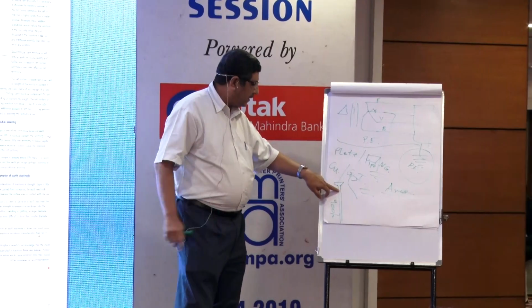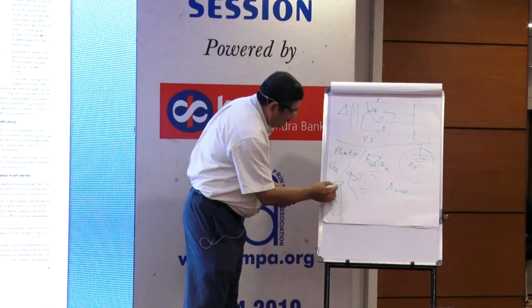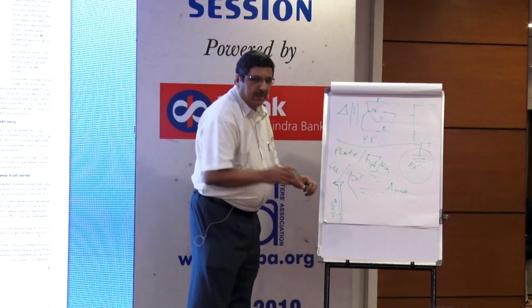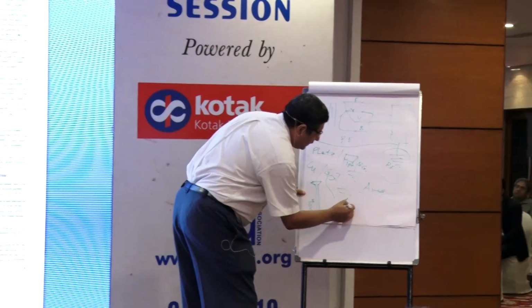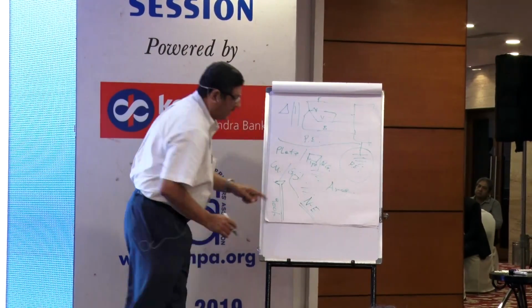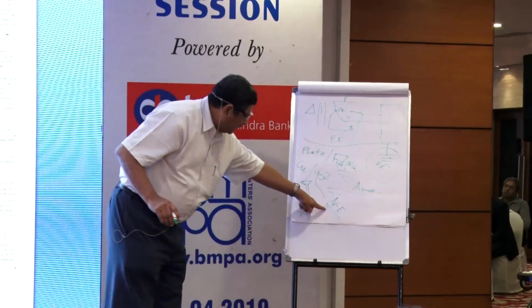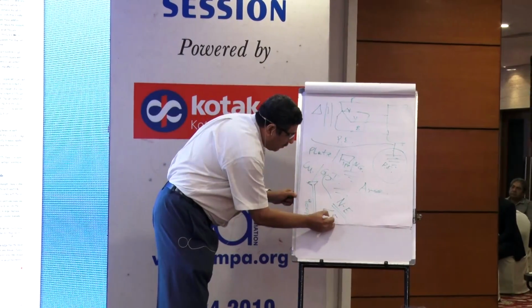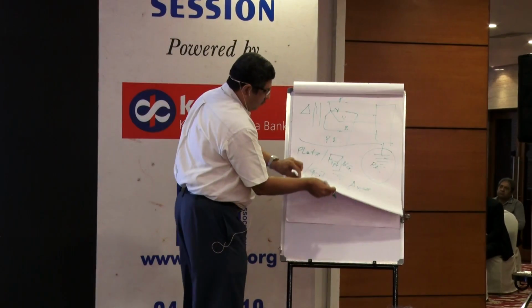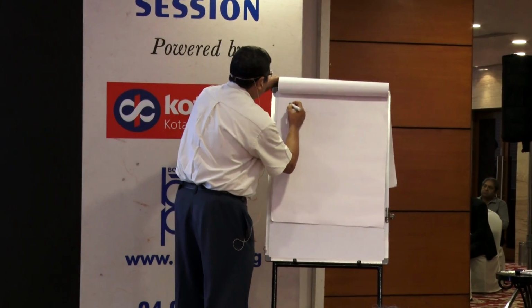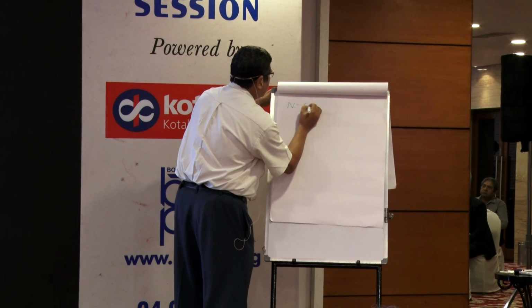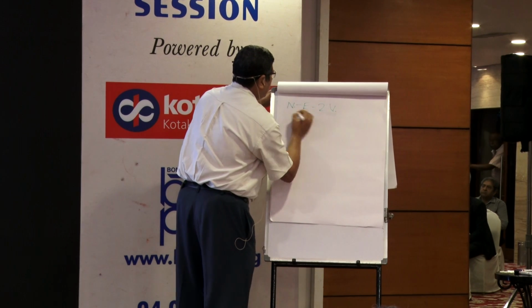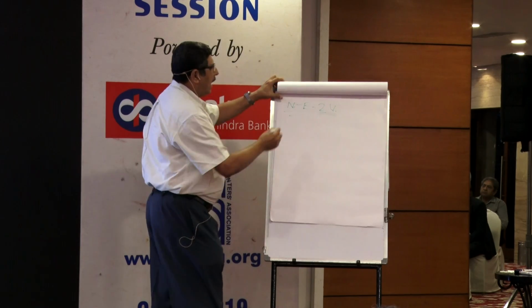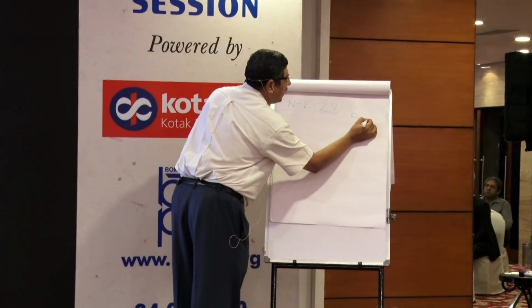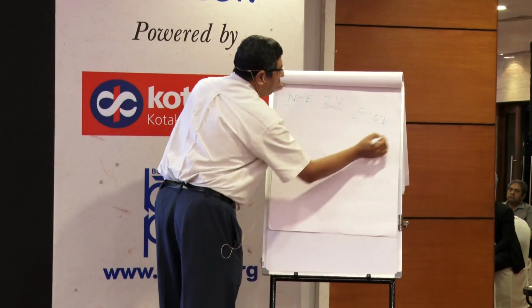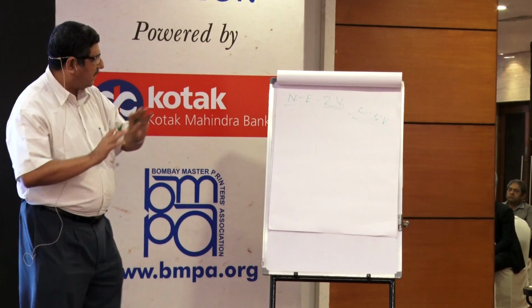Now due to this faulty earthing, there is something called conductance. If the conductance is not okay, you will not get the proper neutral to earth voltage, which is a term we use in engineering. As per IS, this should be less than 5 volts. In my case, I consider it as 2 volts. This is very important. I have seen in my building, which I did last year, a value of 0.5. So anything less than 2 volts is sufficient.